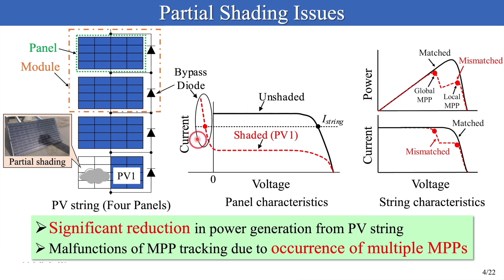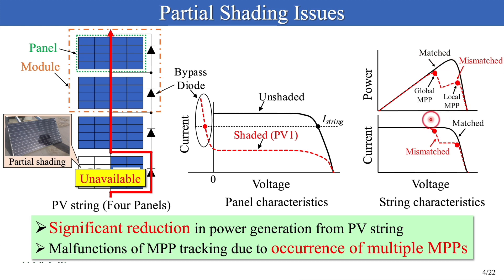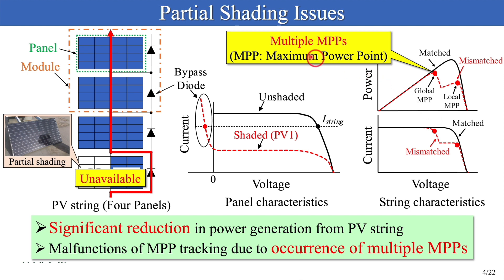As you can see from this figure, the shaded panel is likely bypassed through a bypass diode at a certain current value. Since the bypassed panel no longer contributes to power generation, it triggers a significant reduction in power generation from the PV string. In addition, mismatched panel characteristics exhibit multiple maximum power points (MPPs), including a global MPP and local MPPs. The occurrence of multiple MPPs confuses and hinders the conventional MPP tracking algorithms, because the PV string might operate at a local MPP, which is a suboptimal point producing less power than the global MPP.